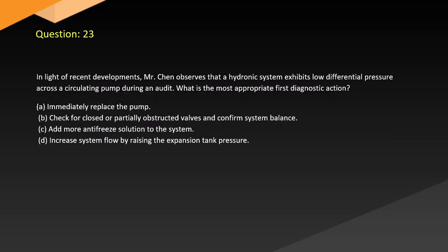Question 23. In light of recent developments, Chen observes that a hydronic system exhibits low differential pressure across a circulating pump during an audit. What is the most appropriate first diagnostic action? A. Immediately replace the pump. B. Check for closed or partially obstructed valves and confirm system balance. C. Add more antifreeze solution to the system. D. Increase system flow by raising the expansion tank pressure.